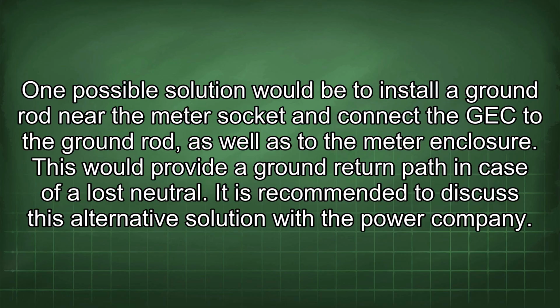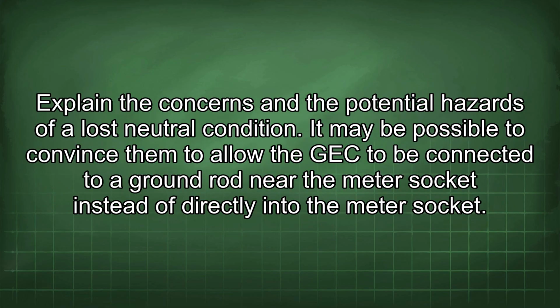One possible solution would be to install a ground rod near the meter socket and connect the GEC to the ground rod, as well as to the meter enclosure. This would provide a ground return path in case of a lost neutral. It is recommended to discuss this alternative solution with the power company. Explain the concerns and the potential hazards of a lost neutral condition. It may be possible to convince them to allow the GEC to be connected to a ground rod near the meter socket instead of directly into the meter socket.